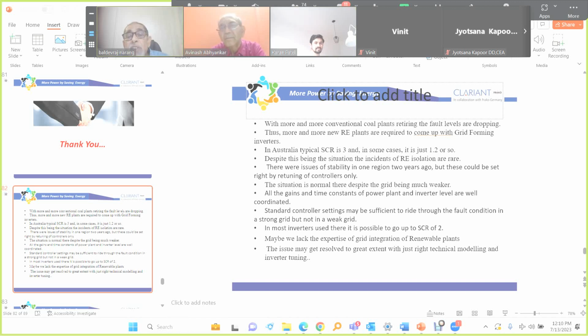So STATCOM installation may not help at all because it will be configured with the PPC. And during fault condition, PPC is out of service, it freezes. So whatever tuning you do for the STATCOM is always configured to supply reactive power instantly. It can cope with that during steady state condition. But during fault condition, it is not available. The PPC itself is not available with which it is configured.